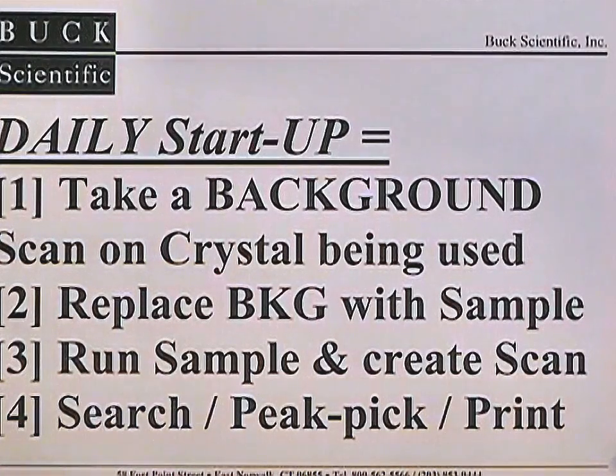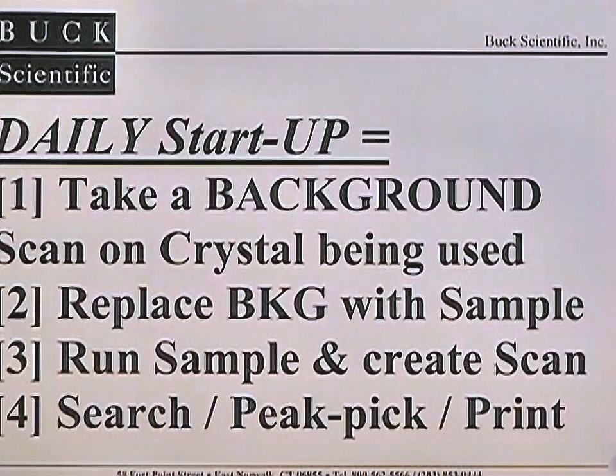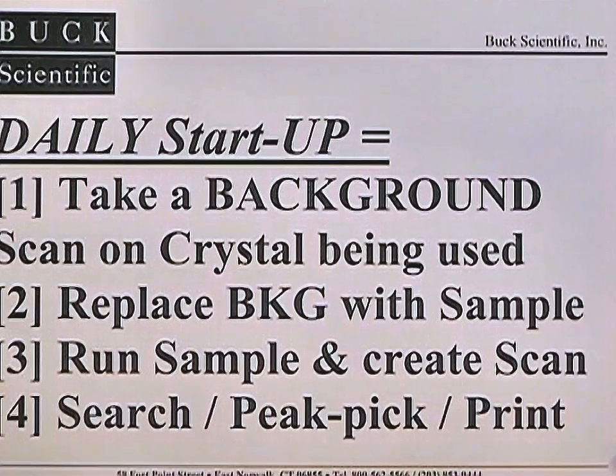As with all spectroscopy software, it is necessary to start the day with a fresh background or reference spectrum on either an open path or the sodium chloride or ATR crystal that will be used for your samples. Replace the background with the sample material, scan the sample, and create your percent T or absorbance spectrum. From that spectrum, you can do search, peak-pick, or print as desired.